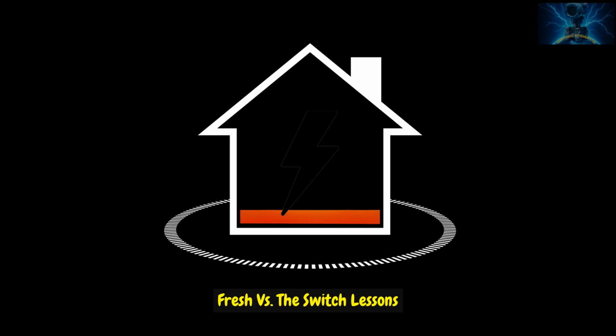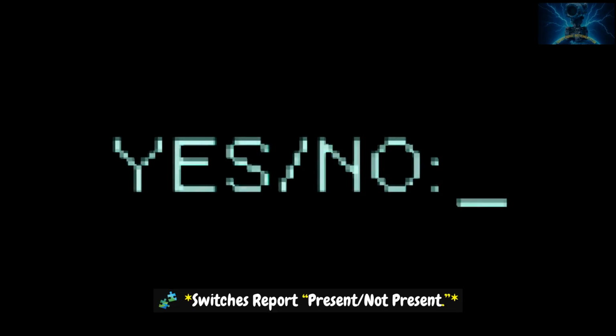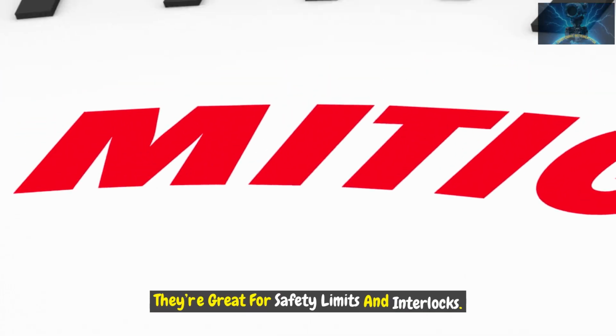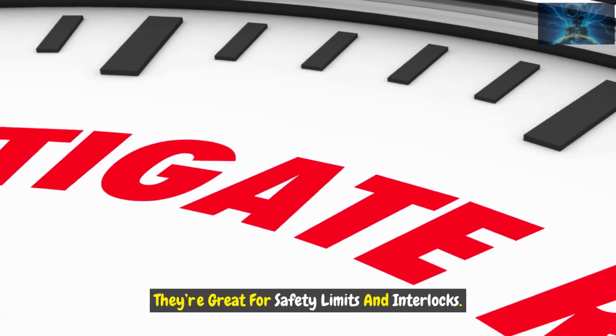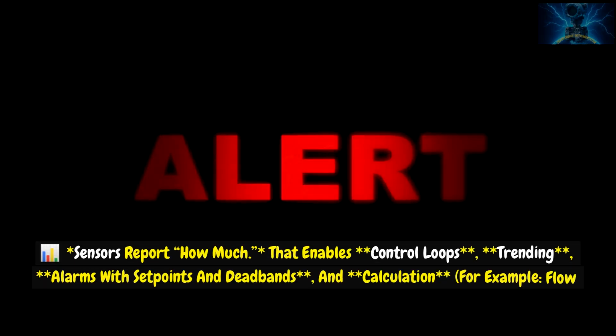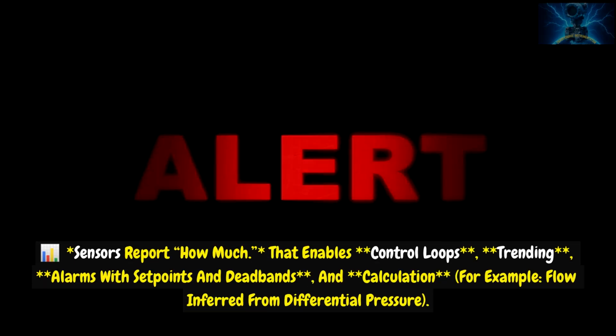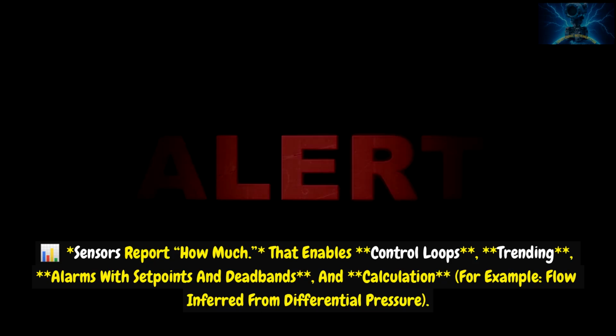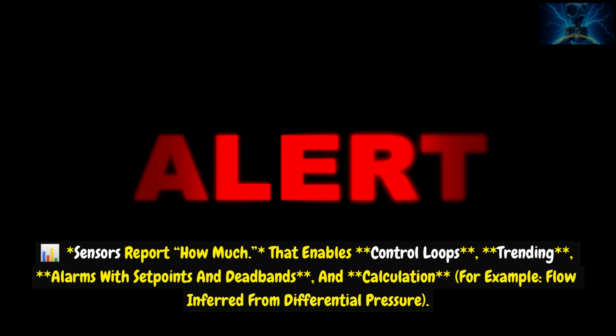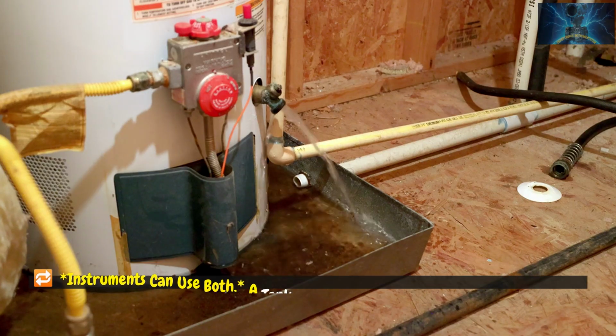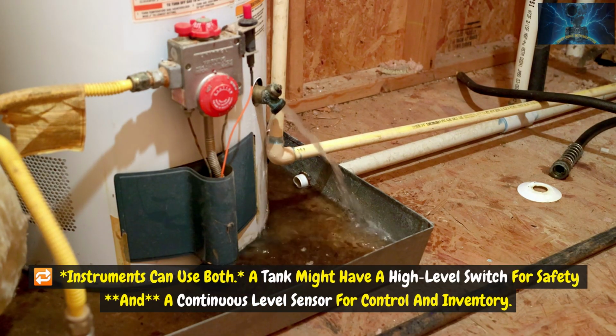Versus the switch lessons, why this isn't a repeat. Switches report present, not present. They're great for safety limits and interlocks. Sensors report how much. That enables continuous control loops, trending, alarms with set points and deadbands, and calculation. For example, flow inferred from differential pressure. Instruments can use both. A tank might have a high-level switch for safety, and a continuous level sensor for control and inventory.